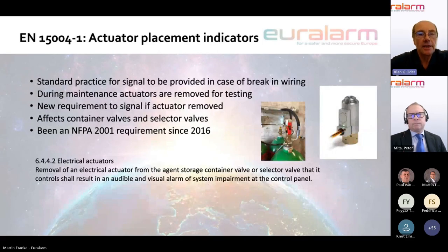So the next one is a requirement in the standard to include actuator placement indicators. Now, for those who've been in the business for many, many years, will fully appreciate that the electrical cabling that goes to the actuators used to release the system are monitored in case there's a break in the wiring. So in other words, if the wiring gets cut, there will be a signal given to the control panel to say that there is a fault indication here. And you can go to the actuator device and you can see that there may be damage to the wiring.